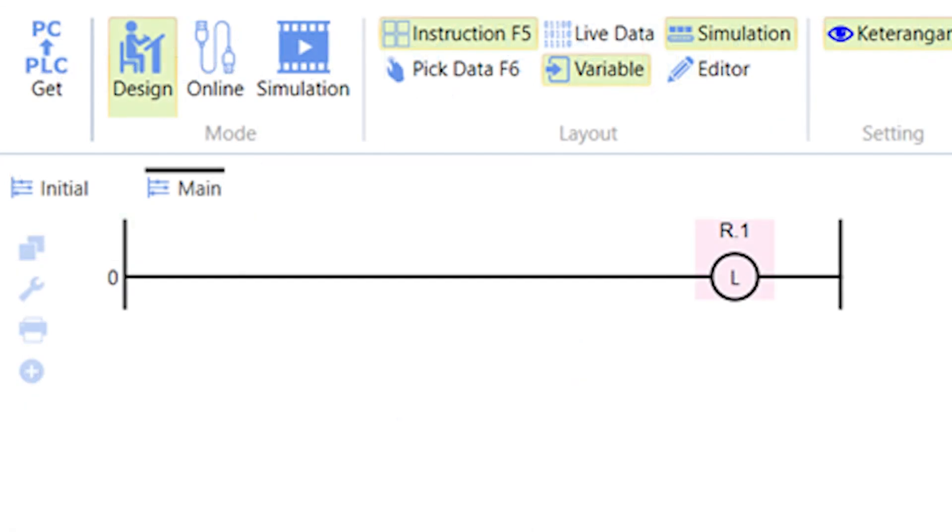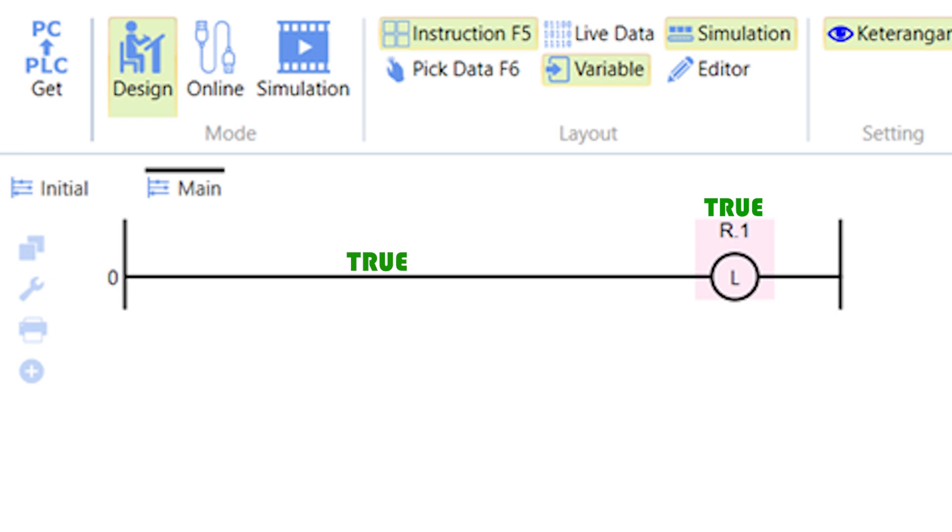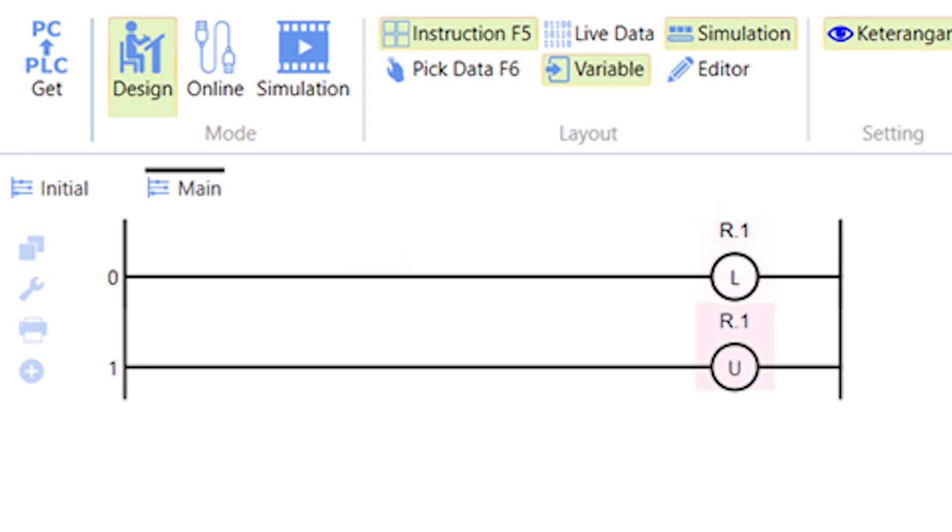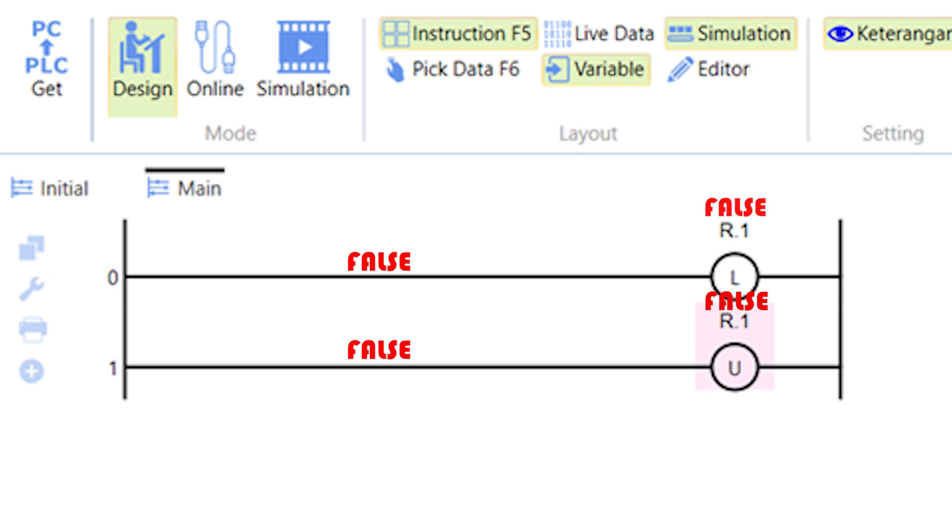The latch coil acts differently from the normal and inverse coil. If the coil variable bit state is initially false and it is changed to true when the rung condition is true, it will remain true even when the rung condition has changed to false. The unlatched coil will be required to change the state of the variable bit back to false.